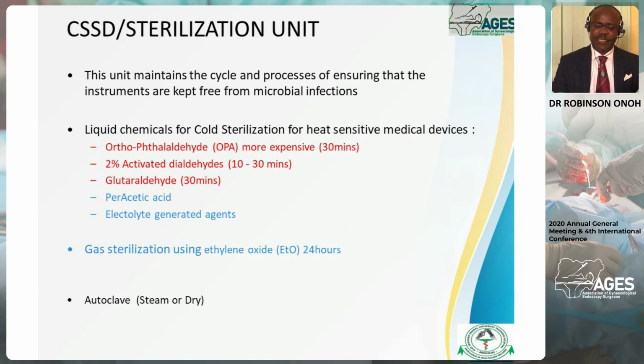We have to understand that laparoscopic instruments, majority of them are heat sensitive. So because of that, liquid chemicals for cold sterilization are used. The orthophthalaldehyde, the 2% activated dialdehyde, glutaraldehyde, peracetic acid, electrolyte generated agents could also be used. Gas sterilization could also be used using ethylene oxide. This takes a longer time than the aldehydes. The autoclave machine should also be there for sterilizing the theater materials and the instruments that are autoclavable and the instruments that are not heat sensitive.